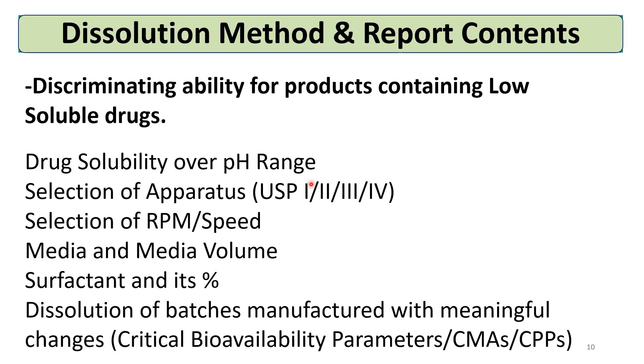The content of this section should include: drug solubility over the physiological pH range; selection of apparatus 1, 2, 3, or 4; selection of RPM or speed — such as 50, 60, or 75 RPM for the paddle apparatus and 50, 75, or 100 RPM for the basket apparatus; media and media volume; and if a surfactant is used, which type and what percentage, justified based on dissolution experiments.